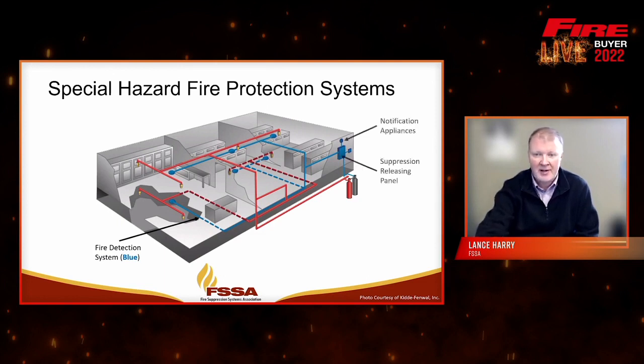The detection system is wired back to a central control panel, typically dedicated to this type of system. This suppression release panel is connected directly to the system and controls when it might be activated. In most cases this panel would be tied back into the larger building fire alarm panel and communicate with it to determine when the system might go off, or impending issues in that area. Also connected to the control panel are notification appliances - horn strobes, buzzers, alarms, all kinds of things to indicate that an activation might be upcoming or has already occurred.